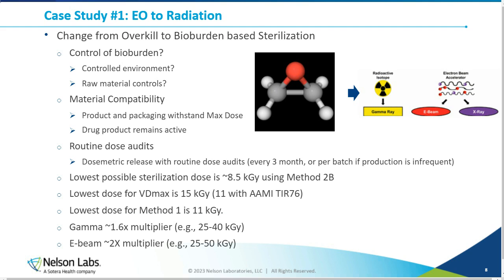So let's jump into our first case study, which is going to be a transition from EO, ethylene oxide, to radiation. This is actually a very big change because we're changing from an overkill-based method where we're using MROs and biological indicators to a bioburden-based sterilization method. So one of the biggest implications is control of the bioburden. Is this being manufactured in an ISO clean room? Are the raw materials being controlled? Are there controls in place for personnel?